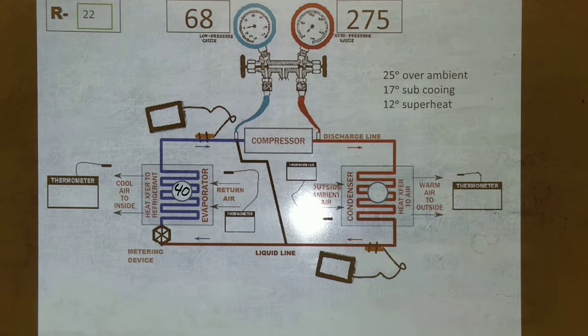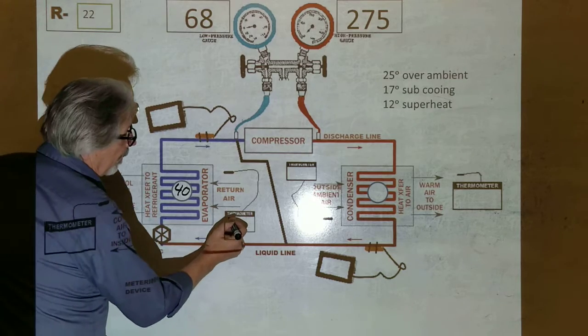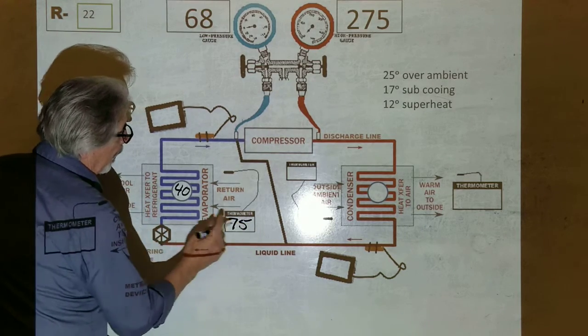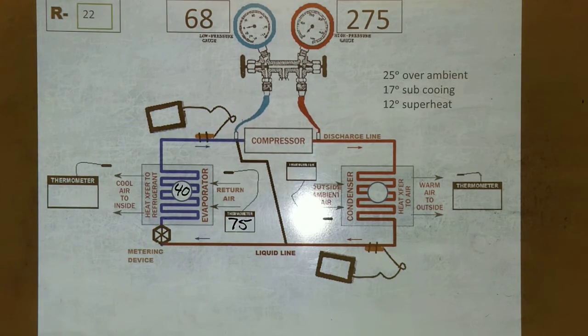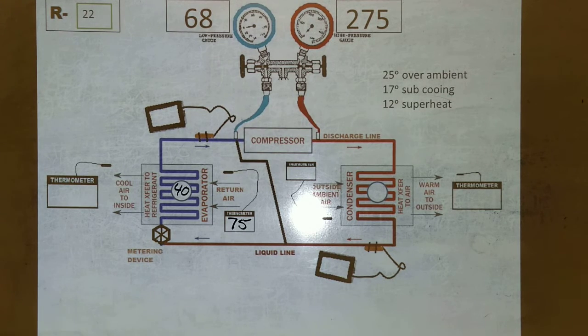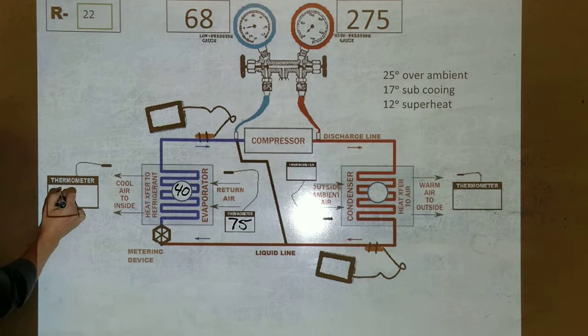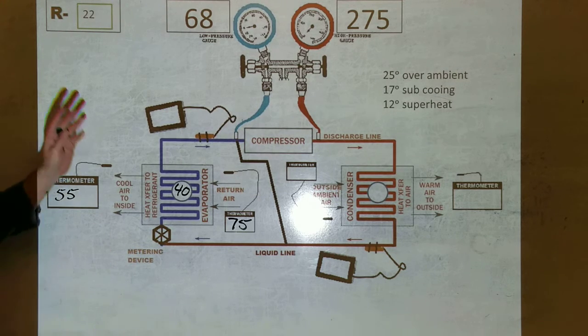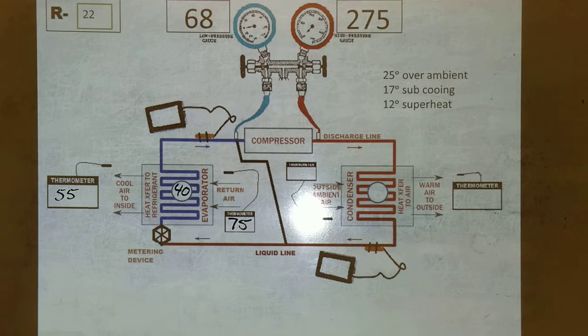In the house, with a 35 degree difference, it would be 75. So our return air is 75? Yeah. We know that because of the 35 degree approach. Okay, and that means our supply air temperature should be 55. So we can actually figure out what we're doing by our pressures, right?